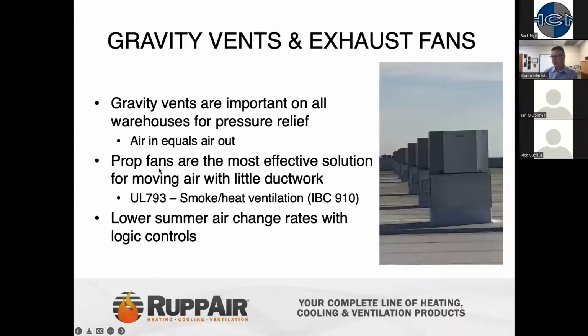Probably the better solution then is to go to having prop fans or exhaust fans in place. Exhaust fans, that you see here on the right-hand side, having those in place is a much better way to approach it. Lower summer air change rates with logic controls.